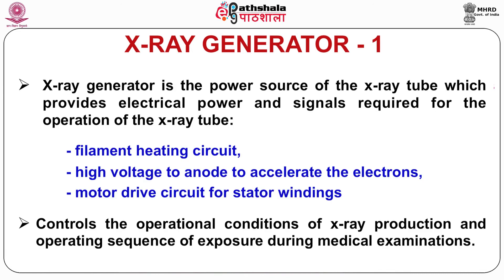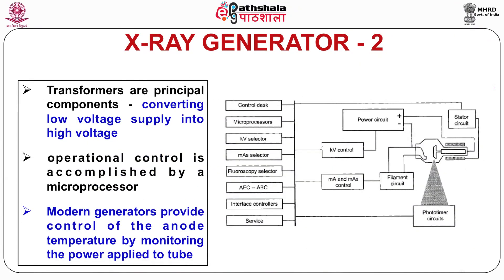Now we will talk about the X-ray generator. The X-ray generator is the power source of the X-ray tube, providing electrical power and signals required for its operation: filament heating circuit, high voltage to the anode, motor drive circuit for stator windings, and control of operational conditions for X-ray production during medical examinations. It supplies current at a high voltage of 20 to 150 kV needed for X-ray production.